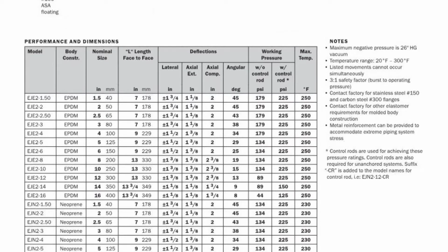The data sheets include information useful in determining dimensional requirements and limitations, as well as maximum system pressures and temperatures where these products can be used. The model names are shown on the left, followed by the corresponding material. You'll note that the third letter in the model name corresponds with the first letter in the material name. Then the size or diameter of pipe for that model, followed by the operating face-to-face length of the flanges. We'll show this shortly.